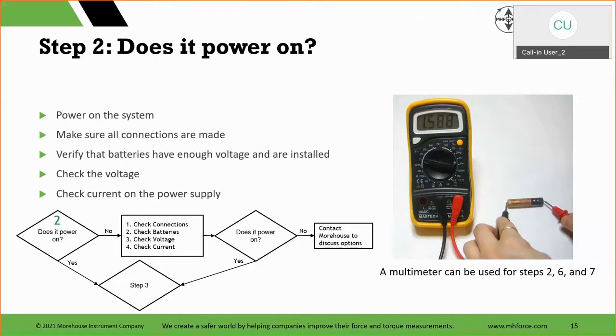You can check the batteries. When we give this class live, we go over a whole section on batteries. Right now, there's a Facebook post on batteries, because we've observed that as batteries discharge, the readings on some of these meters are drastically different than with a charged battery. So something else to check: we've got into the habit of replacing batteries when a customer sends something in new. That is the most repeatable condition when something comes in. Prior to adjustment, put in new batteries and see if it really needs adjusted or brought closer to the nominal value when you have new batteries.